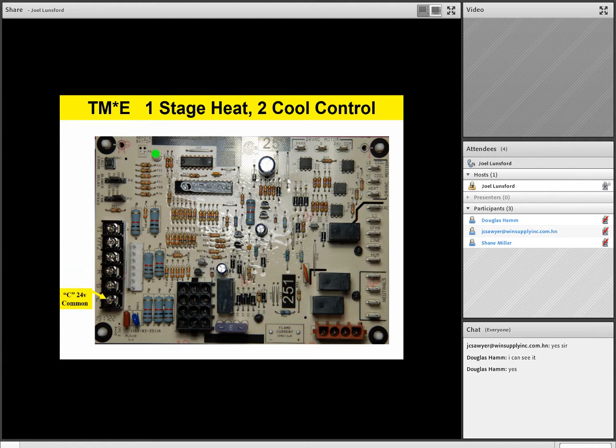Now, right above the low voltage terminal strip, we're going to have a fan speed. Now what this is, is a continuous fan speed selection. So if the homeowner or the building owner goes over to the thermostat and switches the fan from auto to on, this jumper allows the technician to field select what speed the motor is going to run on a continuous fan call. In other words, if I generate a G call on the control board, and that's what you're doing when you go from auto to on at the thermostat, you're actually generating a G only call. If the board sees a G call but no other demand from the thermostat, it'll drive the fan to the speed that's selected on that jumper right there.